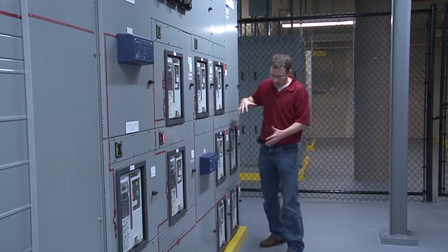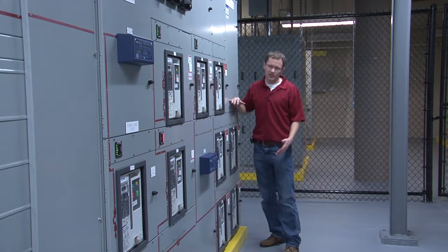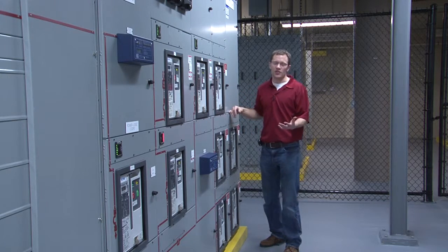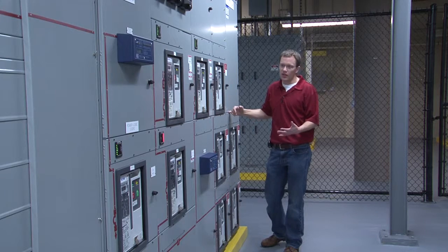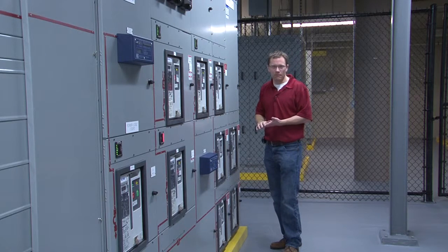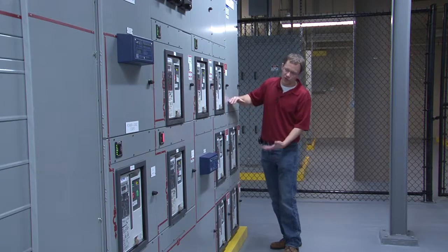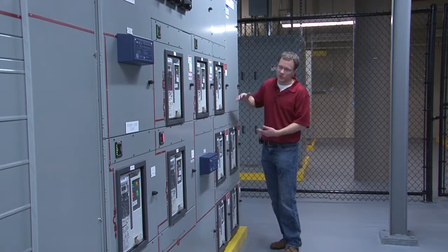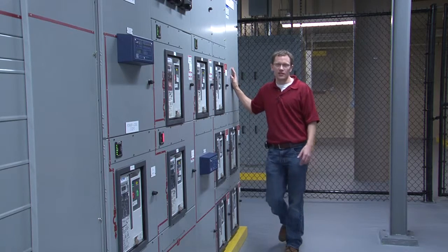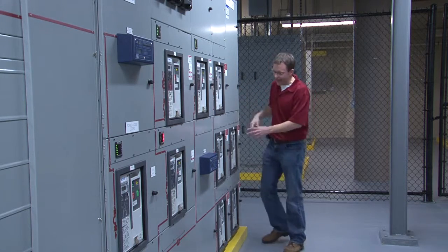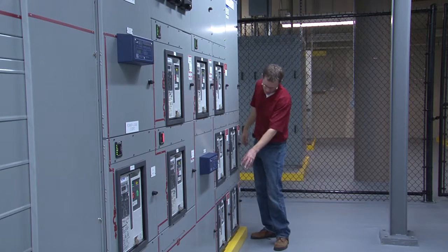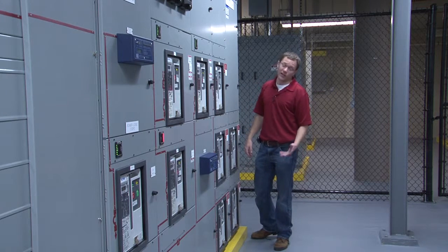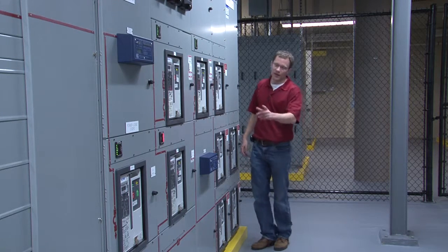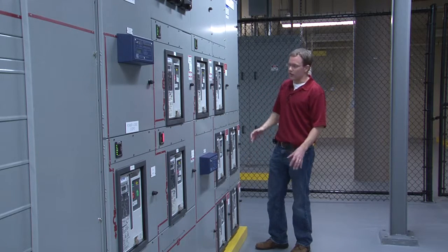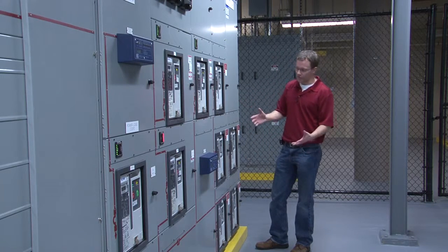What's different about the COD boards in this case versus what you normally see at a substation or a switchboard is normally you have one main input, or you have two mains where one is closed and one's open normally, and then you can swap between the two like we have at the UPS input substations. But at the COD boards, we really have 5 mains. We really have 6 mains actually, because you have a maintenance bypass too. So there's a total of 6 sources for this board.